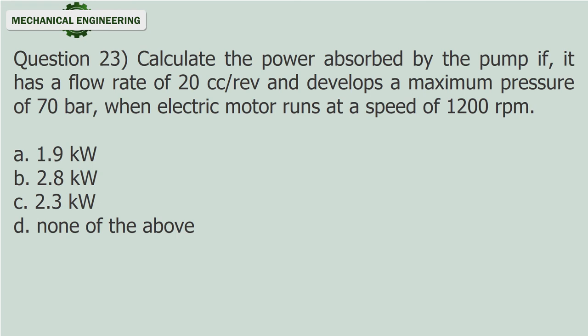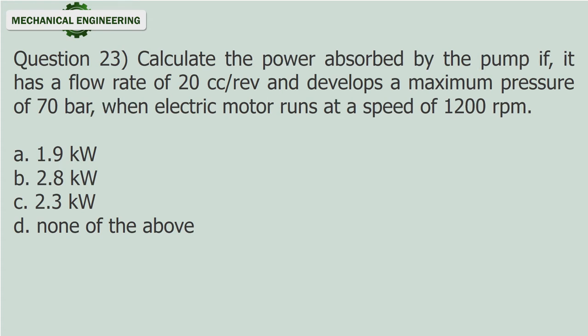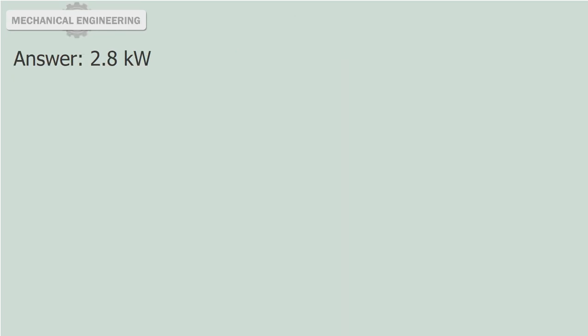Question 23: Calculate the power absorbed by the pump if it has a flow rate of 20 cc/rev and develops a maximum pressure of 70 bar when the electric motor runs at a speed of 1200 revolutions per minute. A. 1.9 kilowatts. B. 2.8 kilowatts. C. 2.3 kilowatts. D. None of the above. Answer: 2.8 kilowatts.